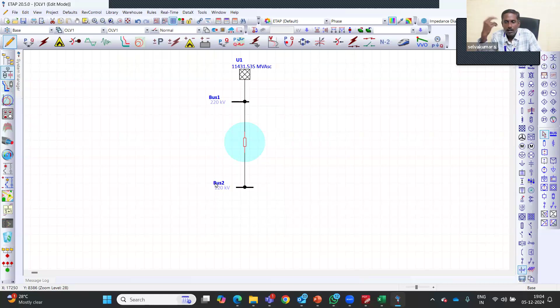So if you're injecting a small harmonic current here by the solar inverter, that will be amplified by this transmission line capacitance—this is the nominal pi model we probably talk about—and it amplifies that harmonics. So the outcome is that when your solar plant starts generating power, huge harmonics may come, and that may result in voltage extremely beyond the acceptable range.